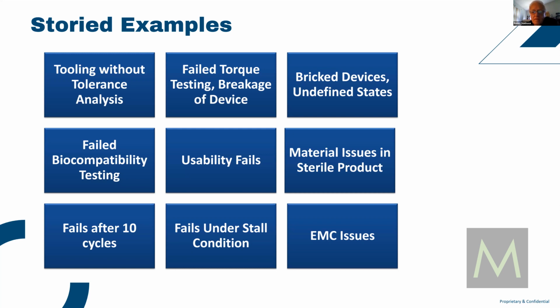Thanks, Joe. Yeah, and actually, along those lines, I have seen the transfer stuff occur because somebody added a tip protector. The tip protector itself, which keeps it from poking a hole, then starts to merge with the Tyvek later, or creates a biocompatibility or sterilization failure due to bioburden issues on the tip protector. So even when you're trying to fix something, you can still create unintended consequences.